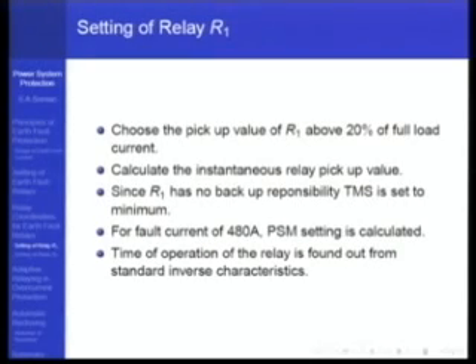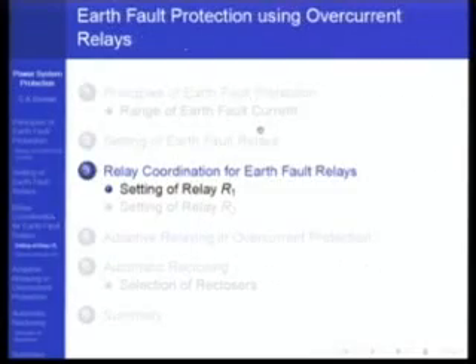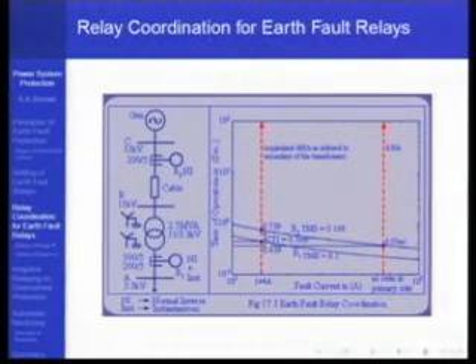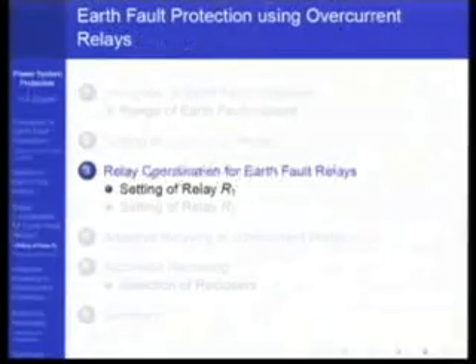Calculate the instantaneous relay pickup value. Since R1 has no backup relay, TMS should be set to its minimum value. For a fault current of 480, the time of operation of the relay is found from the standard inverse characteristic. So the standard steps were followed to find the time of operation of the relay at a TMS of 0.1. Then to that you add a coordination interval of 0.3, and you get the TMS value of 0.739 for this. Now what is the pickup here for relay R2?